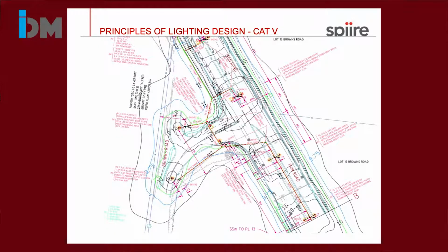Lighting contour diagram. You've got the 3.75 lux contour, which is this blue one. You've also got a green one here, which is a 7.5 lux. In this case here, you've got an intersection. You want to try and keep that. It actually sneaks out here a little bit. I've possibly subsequently adjusted that because I have made a few revisions to this since this contour was done.